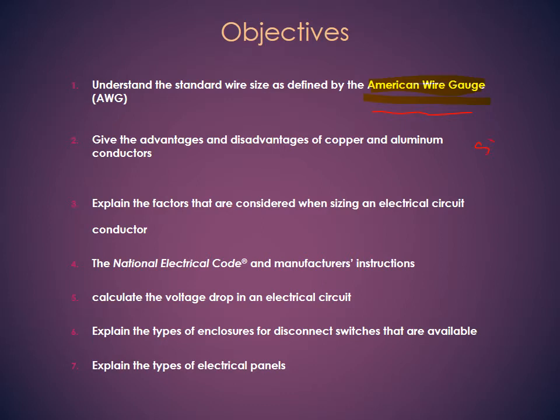So we talk about size of the wire, insulation, and enclosures. We'll talk about that a little bit further. And the advantages of copper or aluminum as conductors. By the conductors, they mean wires. And the factor that is considered when sizing a conductor. So by sizing, we mean the gauge, the length, and so on. And National Electric Code, those are the people who actually make up the American wire gauge and set up those standards.